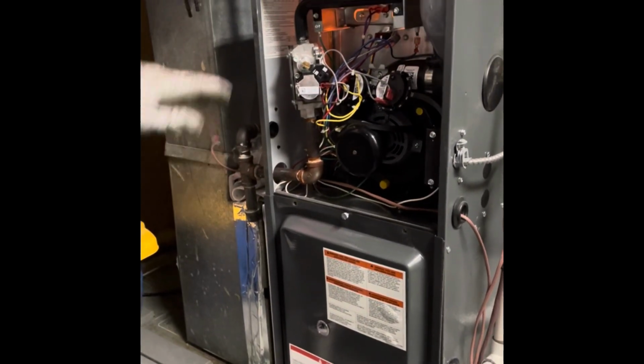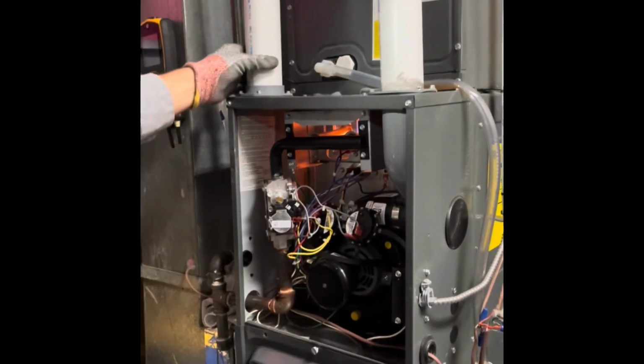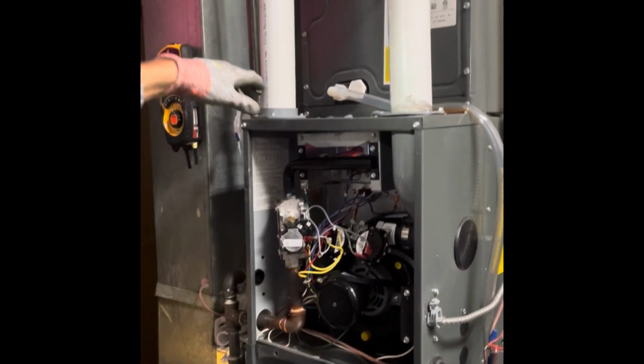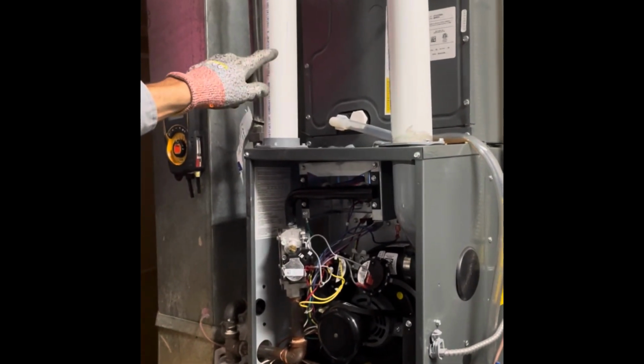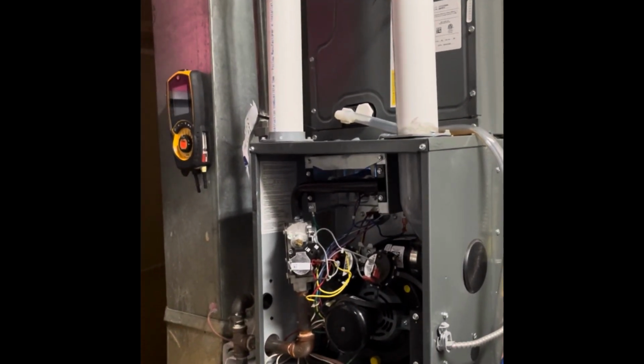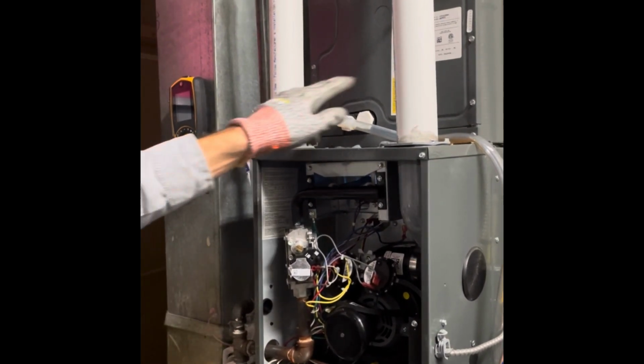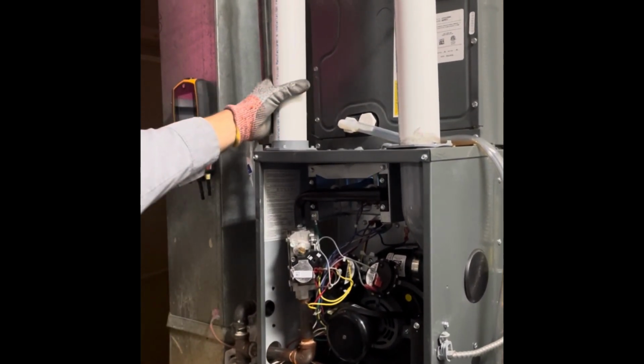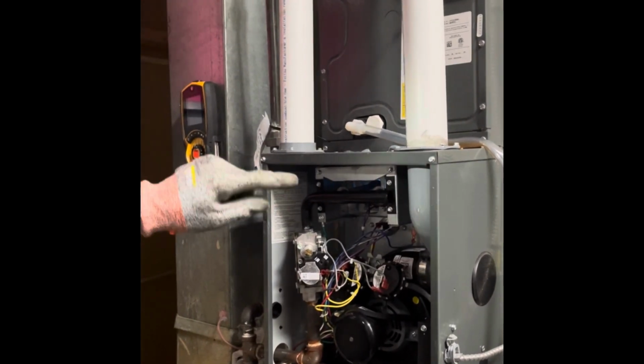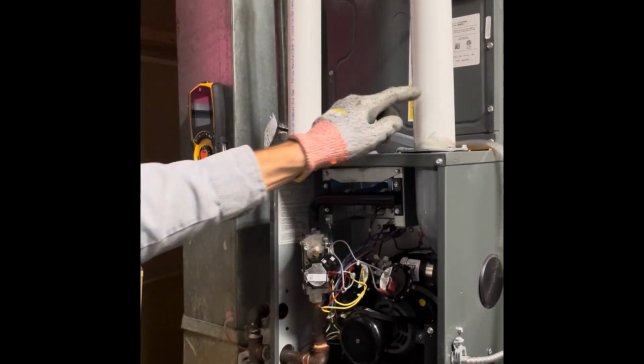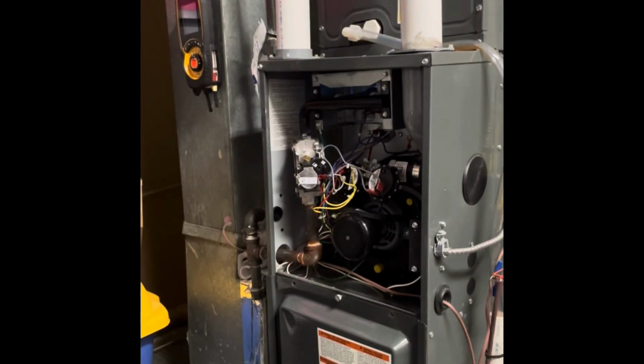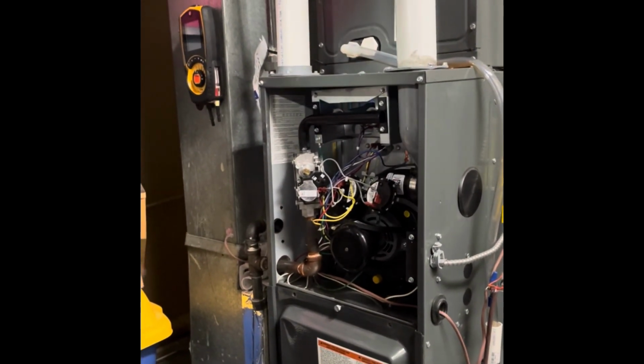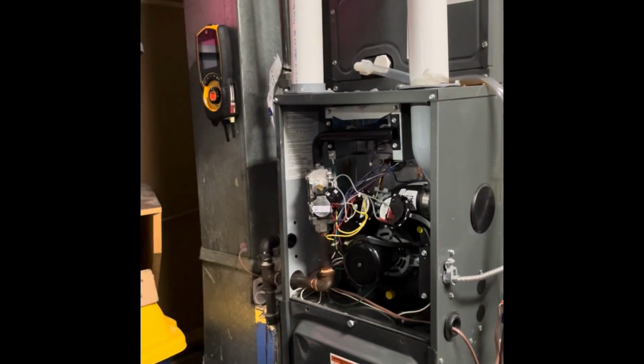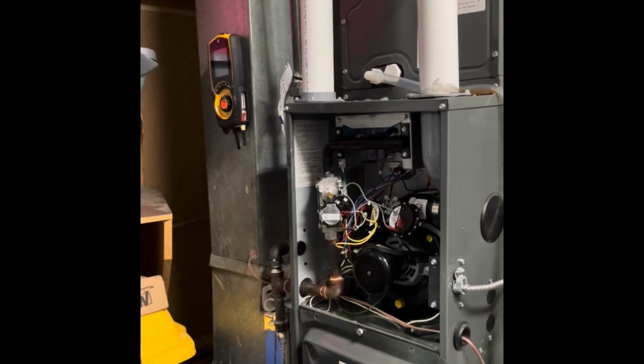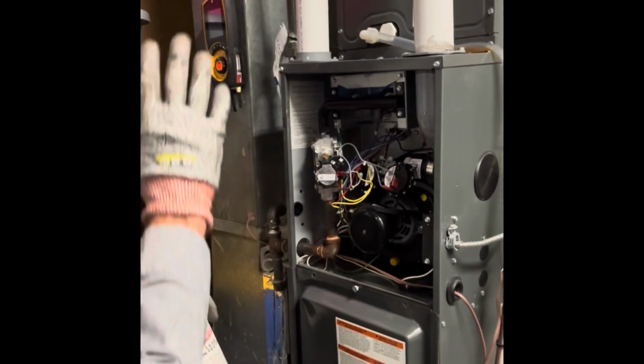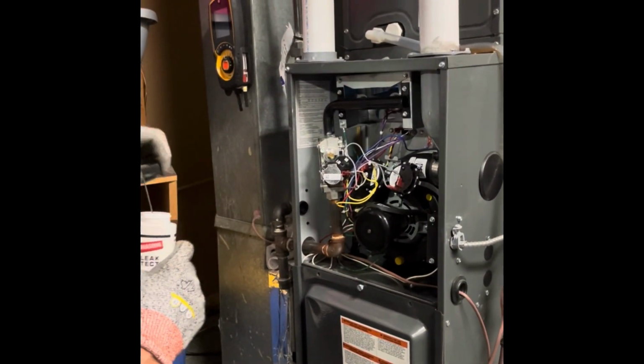You might see, if you're at your house, you might have one pipe going outside, and then you'll have a little stubby pipe here with a fitting on it. That means they're drawing the air from your furnace room. They're not taking it from outside. If it was up to me, I'd like to see a 2-pipe system on everything, because when they're drawing air from a furnace room, we're taking his energy, sending it through the heat exchanger, and it's going right outside. There's that saying, we don't heat the outdoors. Well, in the case that we're taking the air from the furnace room, we got heat going to the outside from the house. So hence why I don't like 1-pipe system. I always want to see 2.